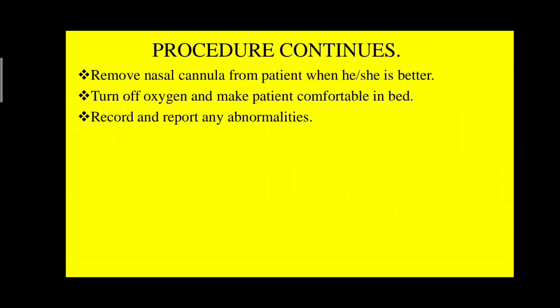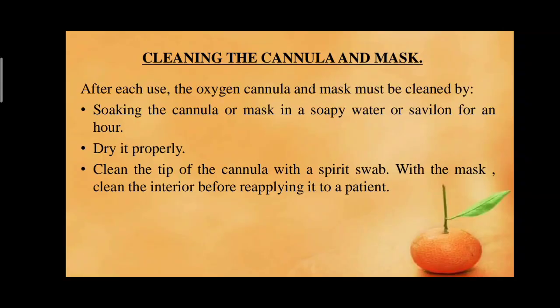Remove the nasal cannula when the patient improves. Regarding aftercare and cleaning of the nasal cannula and mask: after each use, the oxygen cannula and mask must be cleaned properly by soaking in soapy water or Savlon for one hour, then dried properly. Clean the tip of the cannula with a spirit swab, and clean the interior of the mask before reapplying to the patient. This kills microbes and prevents further infection.